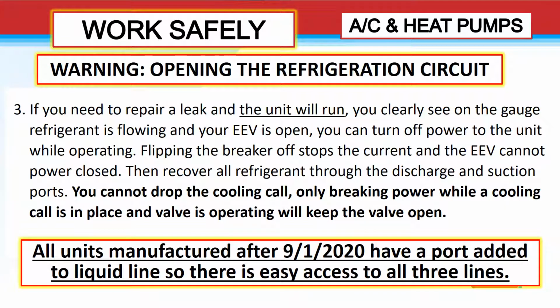If you need to repair a leak and the unit will run, you clearly see on the gauge refrigerant is flowing and your EEV is open. You can simply turn off the power to the unit while it's operating. Flipping the breaker off stops the current and the EEV cannot power close. Then you can recover all the refrigerant through the discharge and suction ports. You cannot drop the cooling call. Only breaking the power while a cooling call is in place and the valve is operating will keep the valve open.